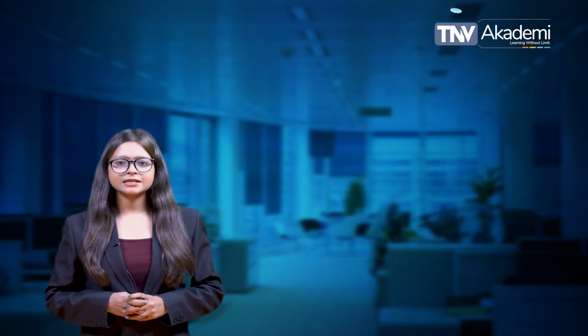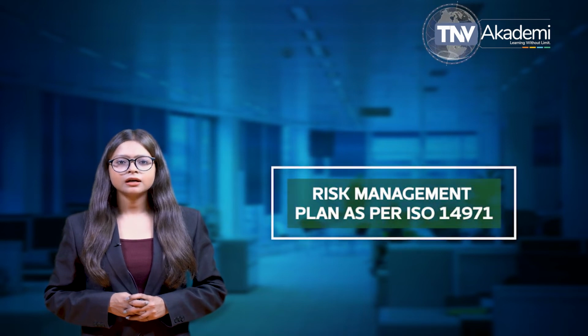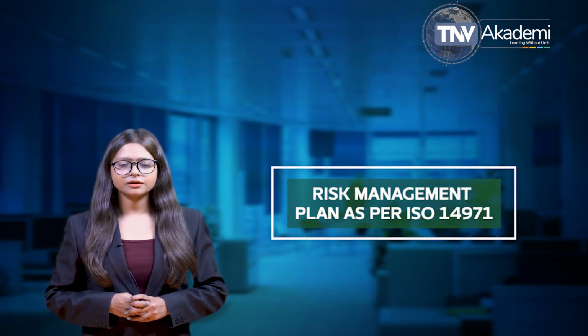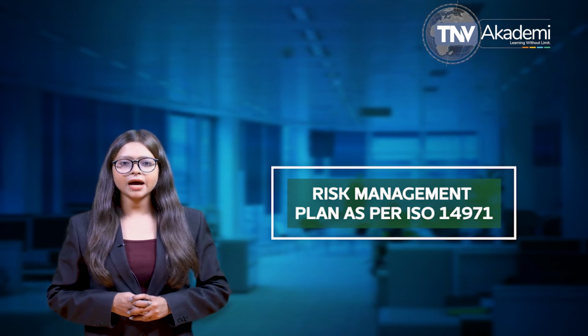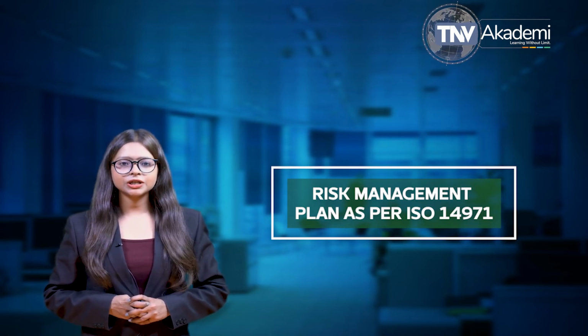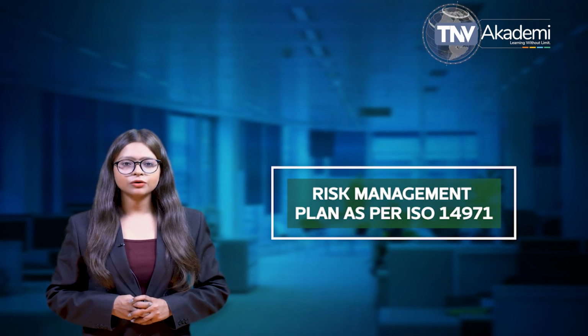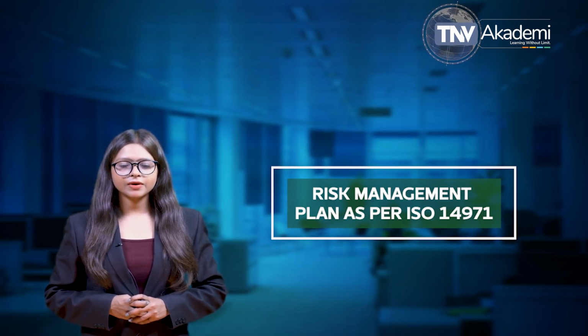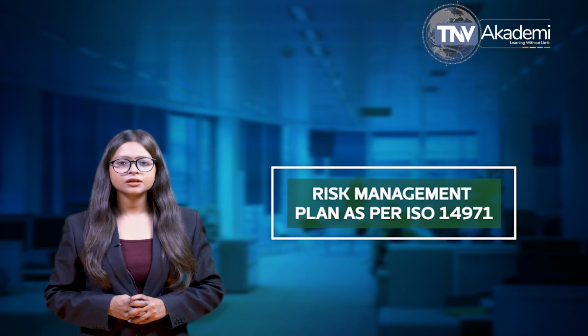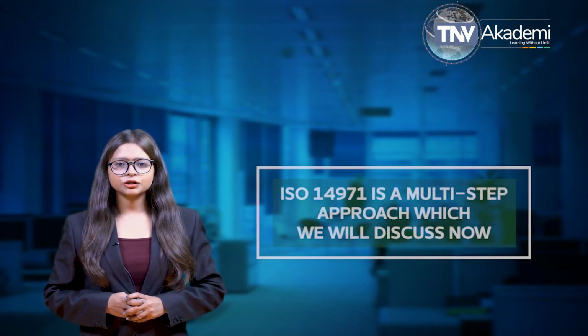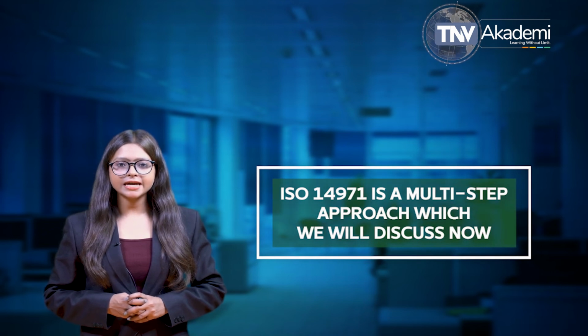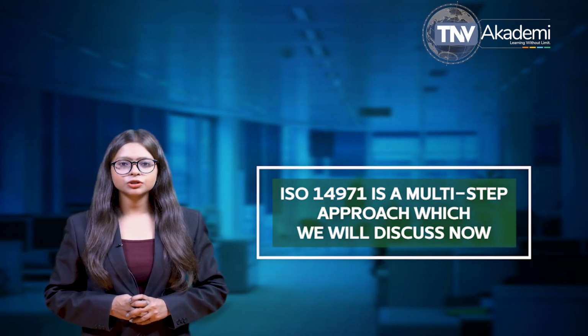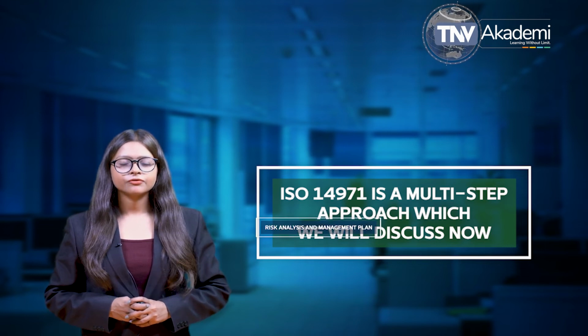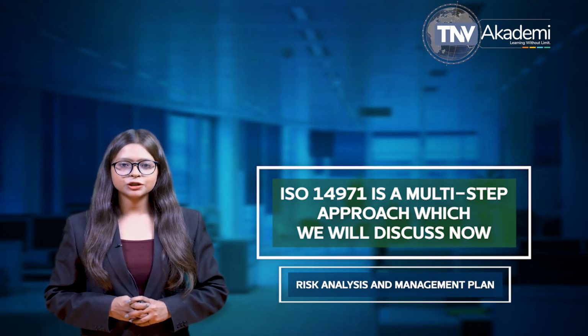Now finally, let us discuss the risk management plan as per ISO 14971. ISO 14971 provides a framework for a risk management plan for your organization as applied to medical devices. From initial analysis to risk control evaluation, the probability and frequency of harm can be assessed, analyzed, and managed. The risk management plan as per ISO 14971 is a multi-step approach which we will discuss now. First one is risk analysis and management plan.